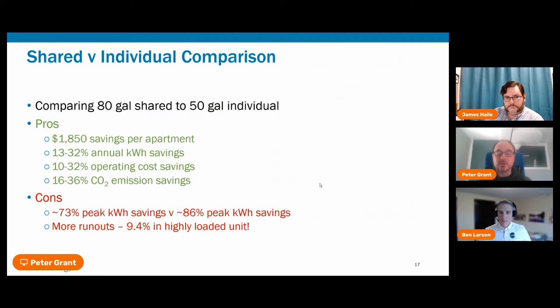But there are cons to this approach as well. As James mentioned, there's more loading on each heat pump water heater, so you're going to have more runouts. And in our most highly loaded unit, 9.4% of all delivered hot water was too cold and considered part of a runout event. So these systems clearly need to be designed well. Also, since these units are more heavily loaded, you can't perform load shifting as well, and you're going to end up with more peak period electricity consumption.